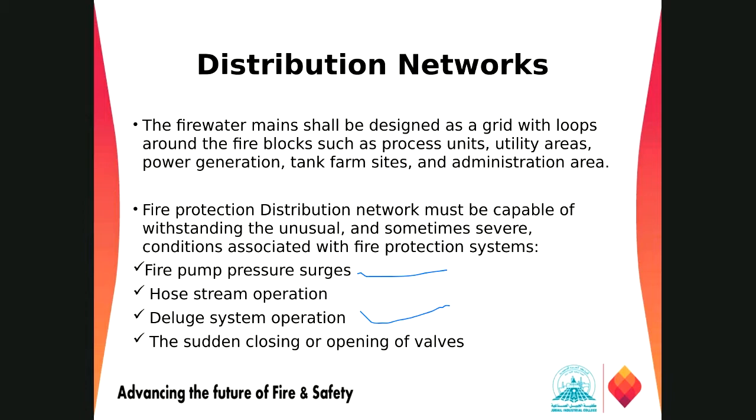And the last one is the sudden closing or opening of valves, right? Any gate valve or isolation valve should not be closed in less than 5 seconds. So we have to close the valve in 5 seconds, not less than that. If the valve closes too fast, the water has mass and velocity, so it has momentum. That momentum will strike the gate of the valve, and at that time there is no flow, so it will put a tremendous amount of force on the piping and the valve. It might damage the system. So we have to keep all those things in mind, right?